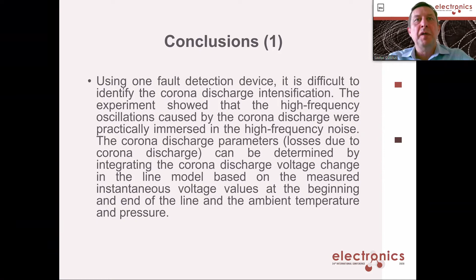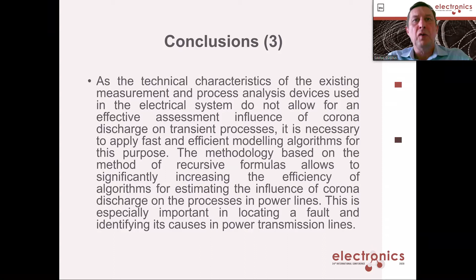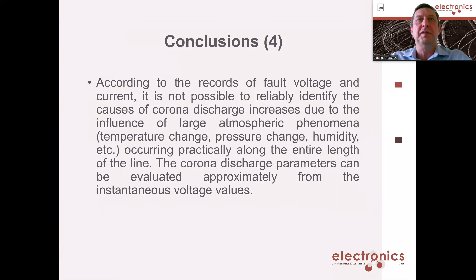Of course, you should know the ambient temperature and the pressure, which are part of the model. Using our proposed model, we can calculate the distribution of corona in the power line, evaluate the situation, and decide if it's necessary to make some additional measurement or inspection on the power line, to avoid a fault and of course avoid losses in the power system. So that is briefly about our research and investigation.